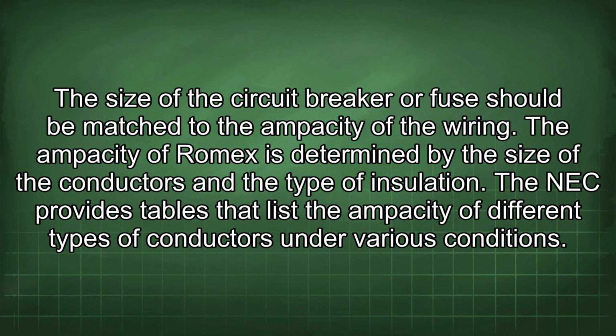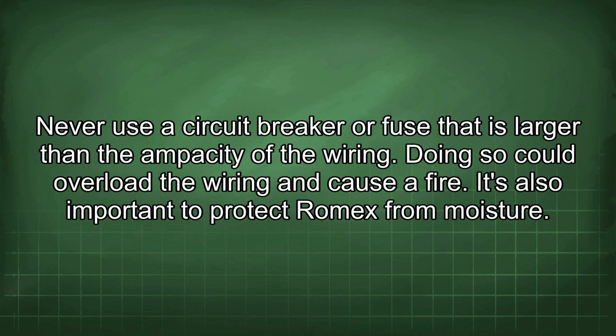The ampacity of Romex is determined by the size of the conductors and the type of insulation. The NEC provides tables that list the ampacity of different types of conductors under various conditions. Never use a circuit breaker or fuse that is larger than the ampacity of the wiring. Doing so could overload the wiring and cause a fire.